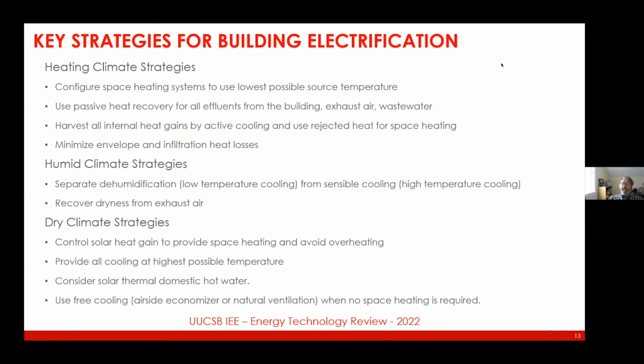So when we talk about the key strategies for building electrification, they do vary by climate. So if we look at heating climate, strategies for electrification there are to configure the space heating system to use the lowest possible source temperature. Most of the older buildings in New York City that have hydronic heating, the systems, the baseboard convectors, the coils and the fan coils or what have you, they're sized for 200-degree hot water approximately. Why is that? Because that is the lowest first cost alternative.